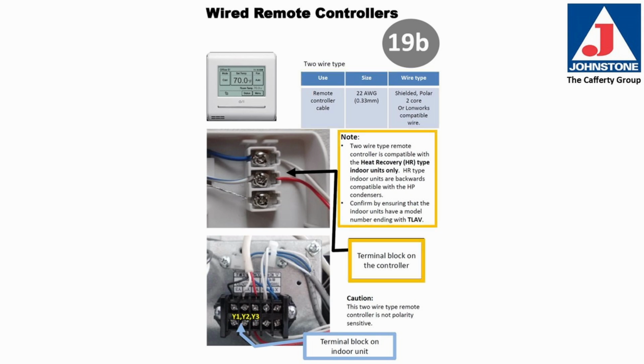2-wire type remote controller is compatible with the heat recovery type indoor units only. Heat recovery type indoor units are backward compatible with the heat pump condensers. Confirm by ensuring that the indoor unit has model number ending in TLAV. Here's a terminal block on the remote controller. The 2-wire type remote controller is not polarity sensitive. Here's a picture of the terminal block on the indoor unit.